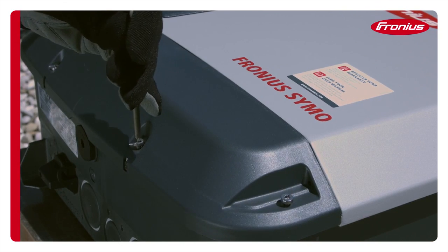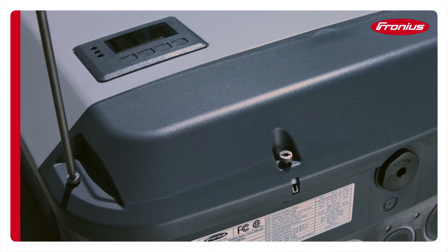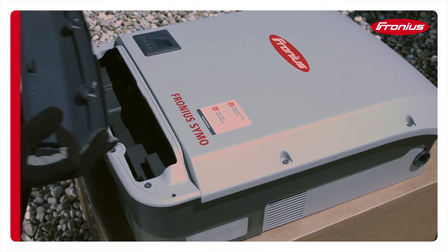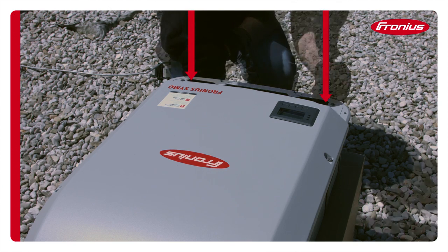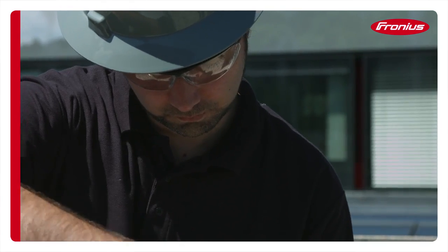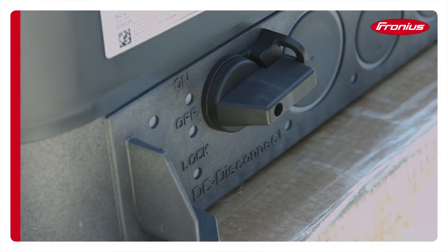Use a T25 Torx driver to remove the four screws on the Datcom cover. Release the two securing screws that hold the inverter to the mounting bracket. The inverter can be released from the mounting bracket when the DC disconnect switch is in the off position.